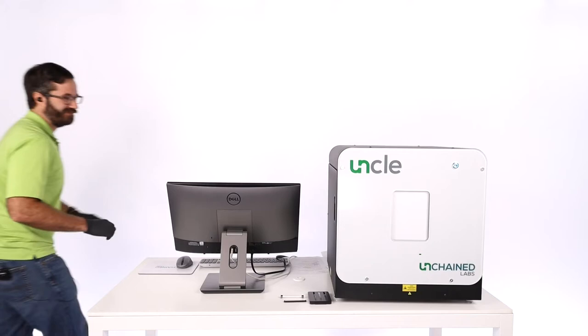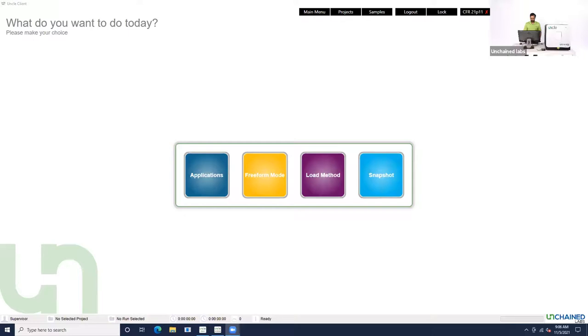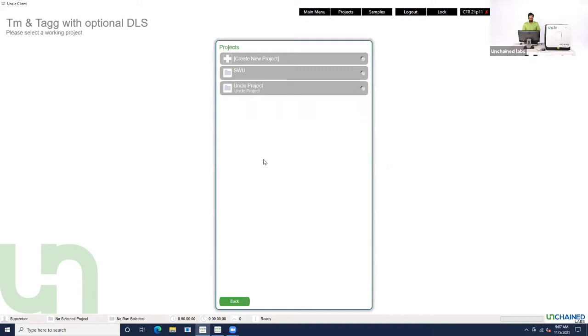Now I'm going to walk on over back to the instrument and show you how to set up an experiment. I'm going to share my screen so you can see the UNCLE client software — the software you use to control UNCLE and do everything you need to do. We'll go to applications and go to Tm & Tagg with optional DLS, which is the experiment we're going to be running. This is what we typically use, and about 90% of our customers are using it to look at protein thermal stability.